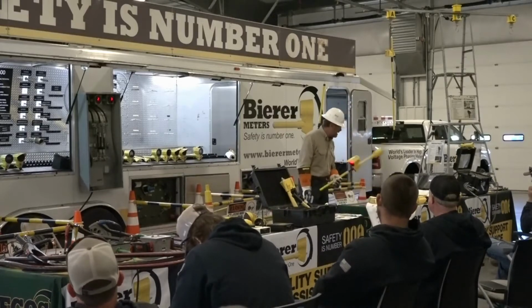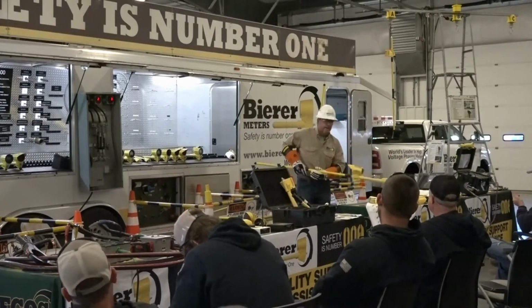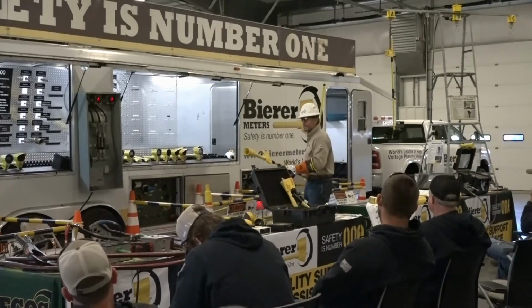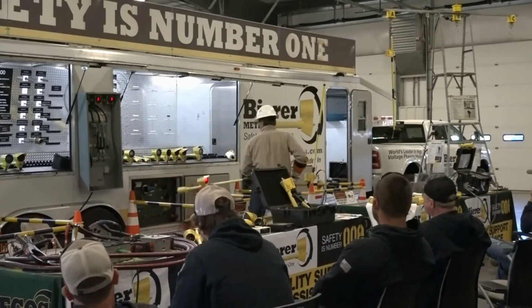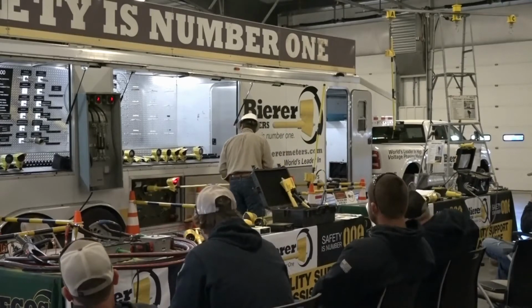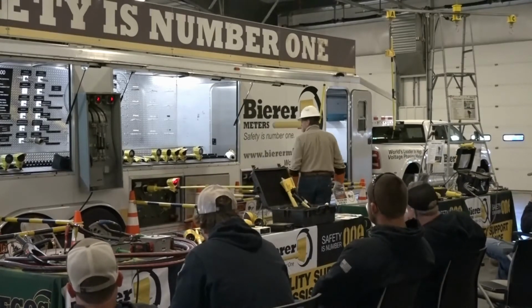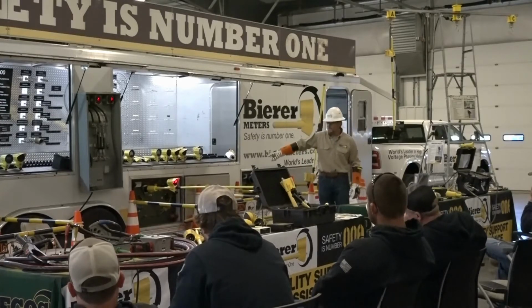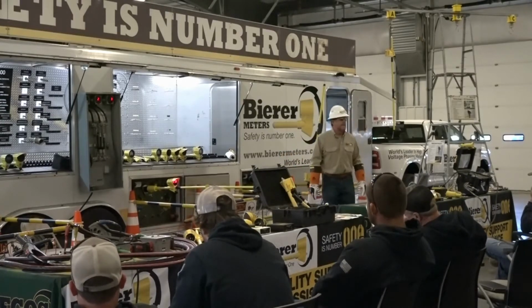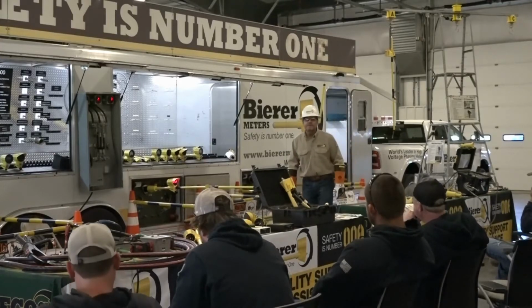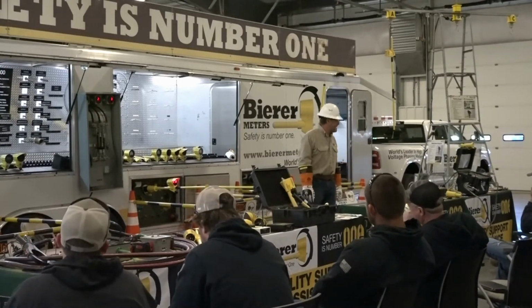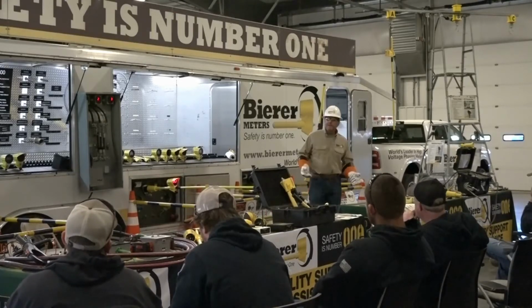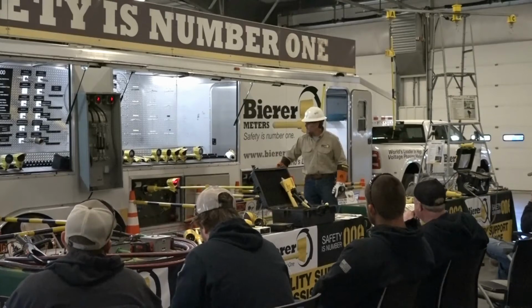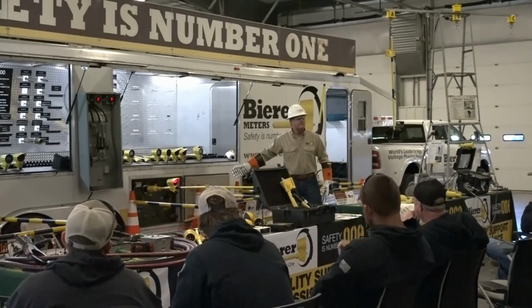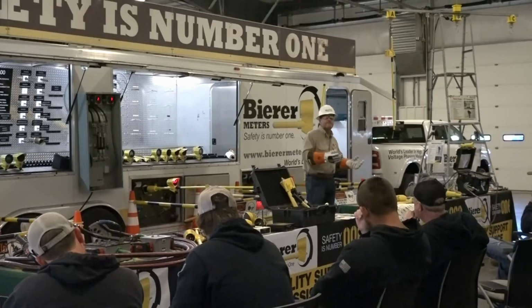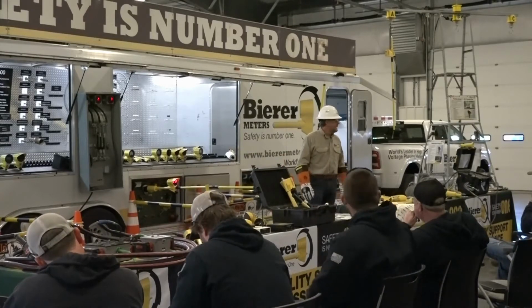We've got our direct contact detector, URD. These overhead lines are pretty low to the ground plane, so it's reading a little high because the meter head is close to the ground plane. It's a 19.9, so we expect it to read a little on the high side because of that, and because we've got a trailer close by, maybe a closed cabinet. We know how this works, so it's expected, but we know we're good.